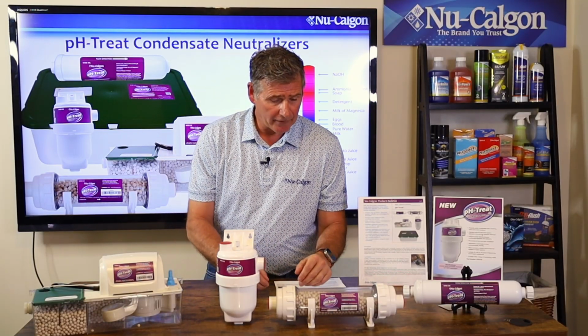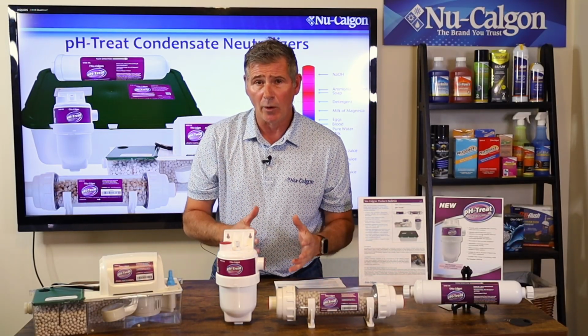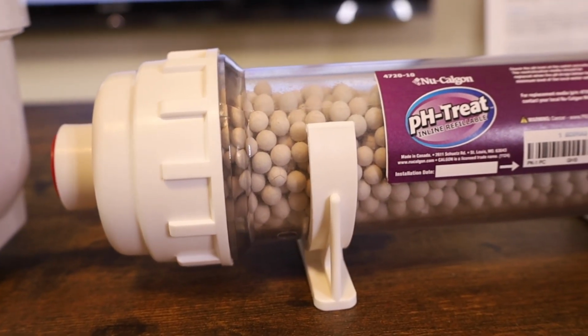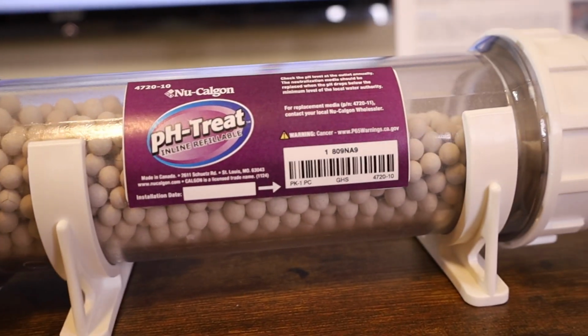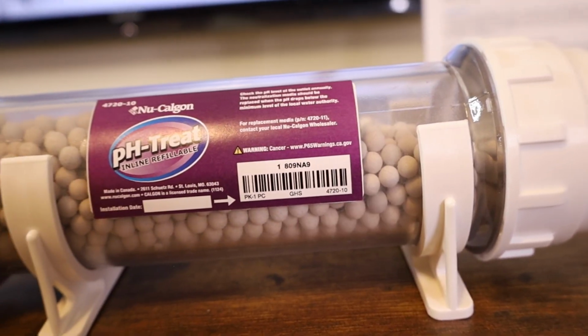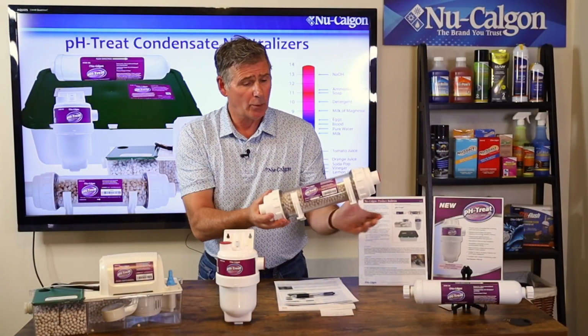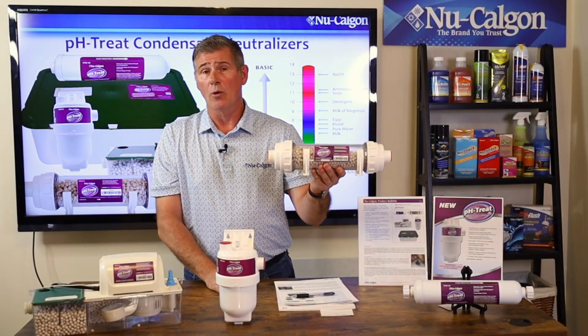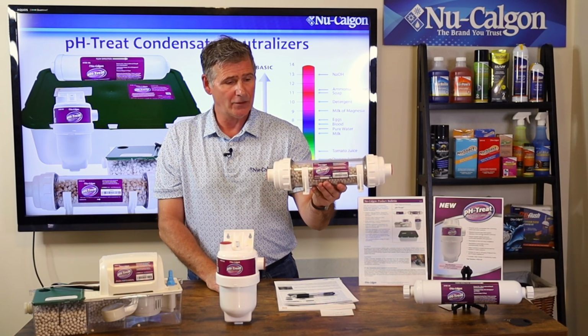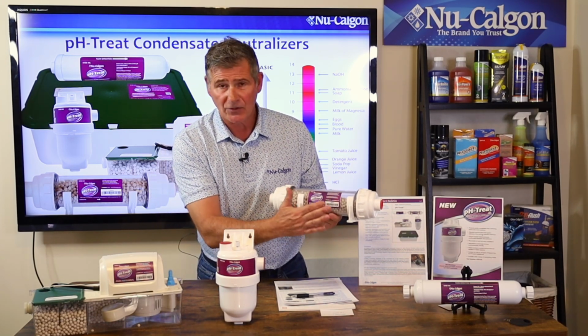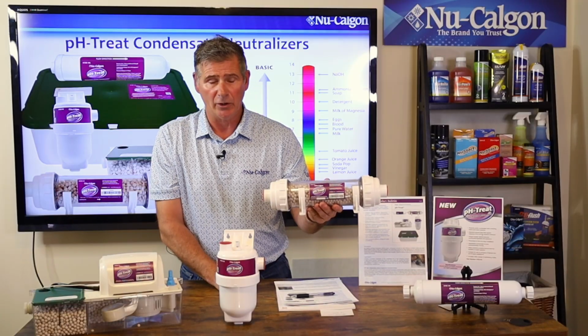The next one we have here, these both actually will do up to a 400,000 BTU system, or a system that does approximately 1.6 gallons per hour worth of condensate flow. And this one can be mounted either vertically or horizontally. You have that choice with this one, and all of these will have an arrow on the sticker letting you know the direction of water flow in them.